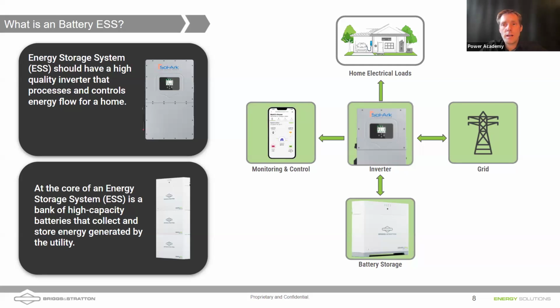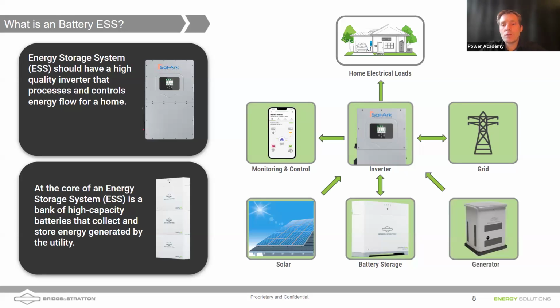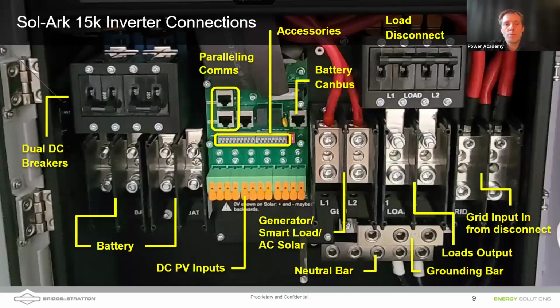So that's essentially what an inverter does. The batteries themselves are DC batteries. They're 48 volt nominal. The inverter has the ability to manage different power sources. So we could bring in solar, we could bring in a generator, and we could start that generator at specific times. Maybe we only want to use that generator when the battery gets low, right? So there are ways that we can manage power with the inverter, and we're going to be talking about those.